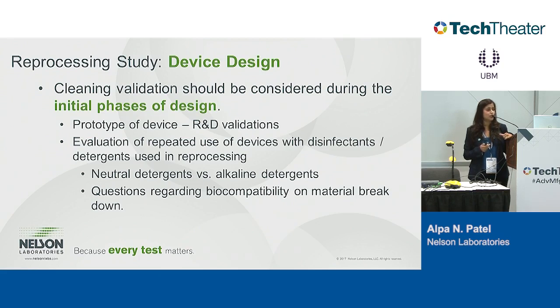Evaluation of repeated use of devices with disinfectants and detergents. As you know, it's reusable, so these devices will be used multiple times. It might be 10, it might be 15, it might be 100, it could even be 500. We have validated a device that has been reprocessed 500 times. And you want to see the history: will it withstand that many times, or will it start to break down? At what point does the device start to break down?